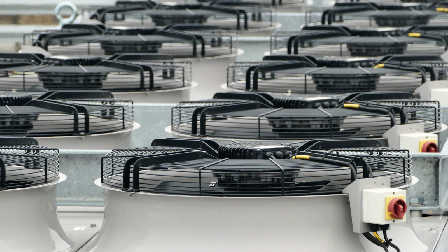Some of the most damaging refrigerants are being steadily phased out in favour of some with far lower GWP values. R32 refrigerant has become a popular alternative, but this still has a GWP of 700. Some systems are compatible with things like ammonia or CO2 itself, and they're becoming much more popular in large commercial heat pumps.